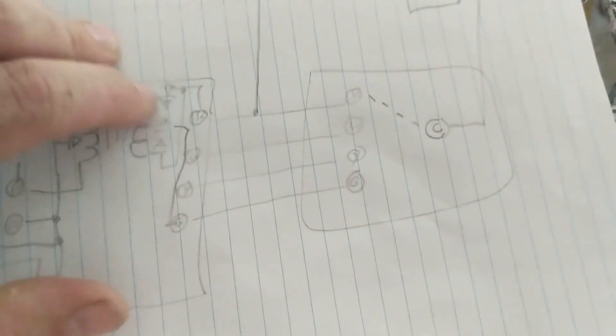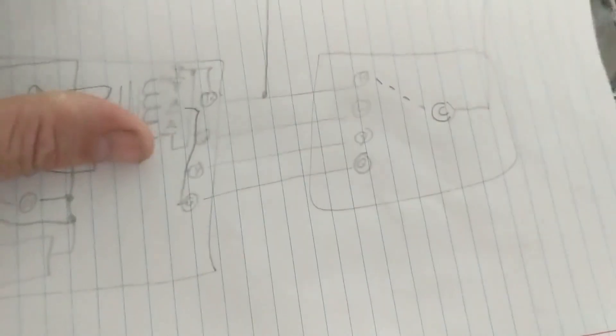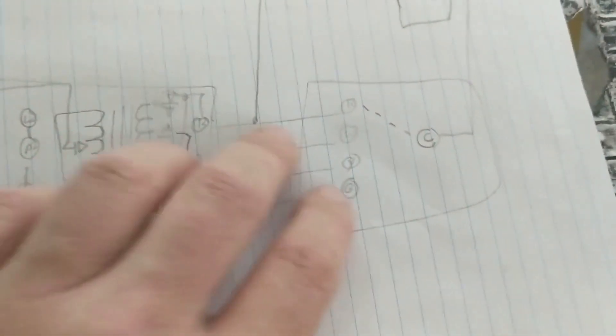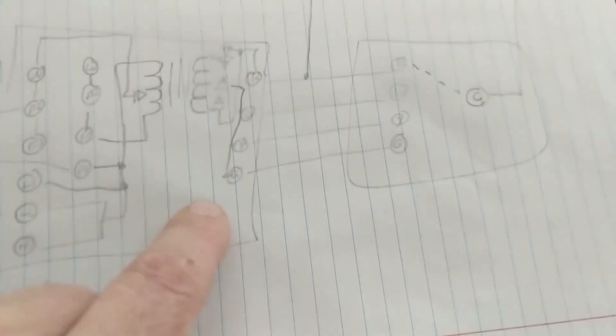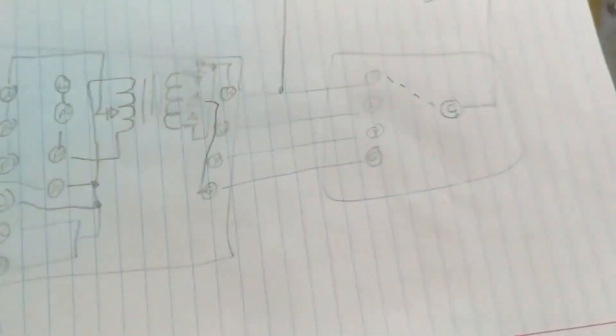If you apply power here, it just goes through this way - it's never going to back out this way and double power this thing and go some weird voltage or something. This is actually a really smart design. I'm surprised they don't give you an option for a 24-volt power supply or even just a common wire assembly in general. I mean, it would be just as simple to hook up something in this general area that's already pre-wired up here, and all you have to do is take your fifth wire down and hook it to your common.